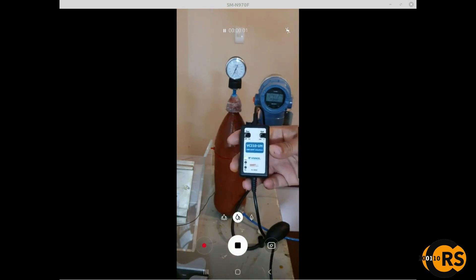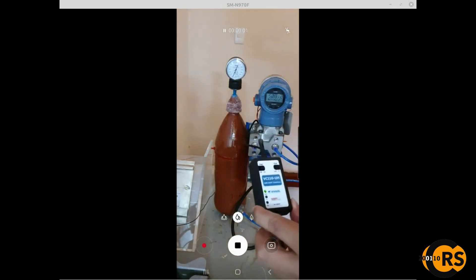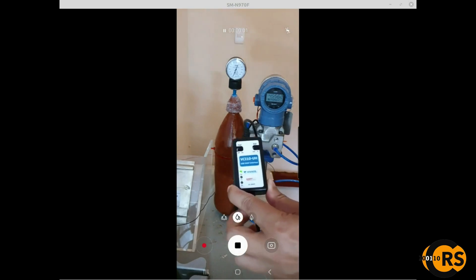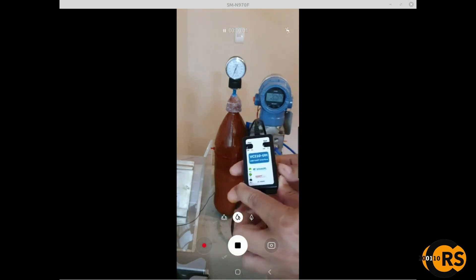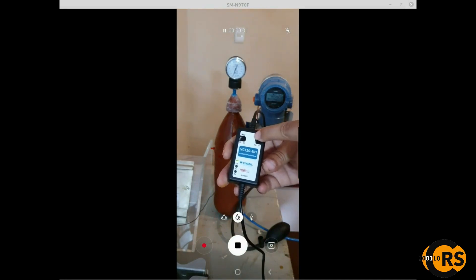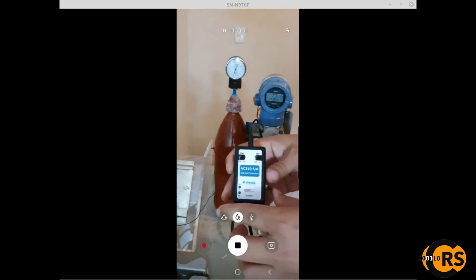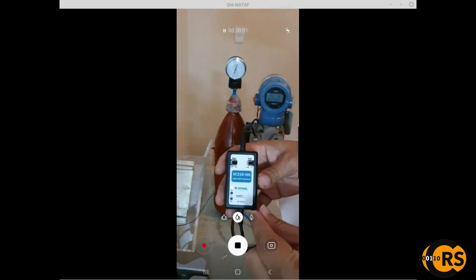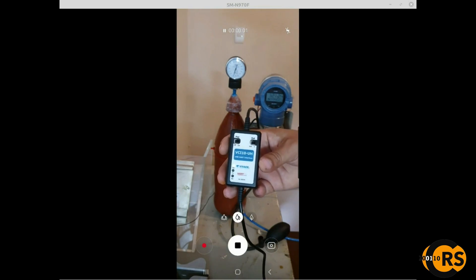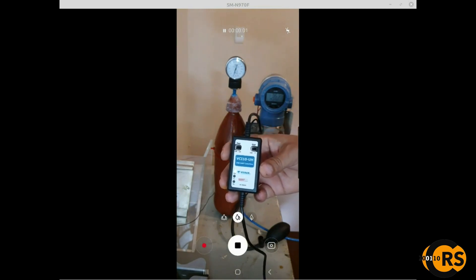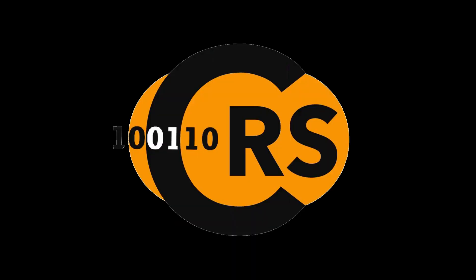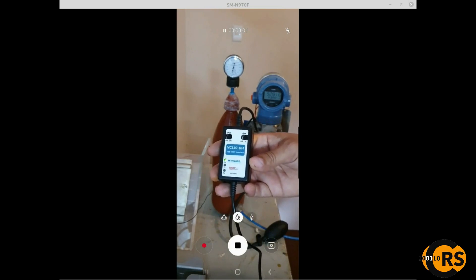This setup is very good for transmitters. If you have, for example, an actuator like a positioner, you should put the output in milliamps — it's going to supply with a minimal current in milliamps and you can test the positioner via HART. You can open or close the valve. Okay, let's see how it works.